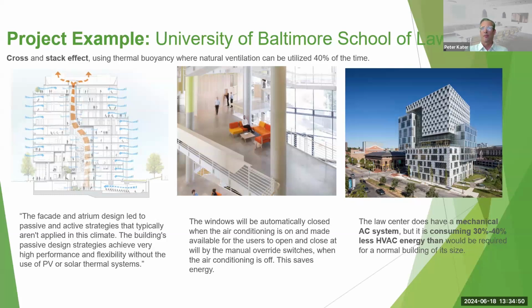Now, in this particular project, they opted not to use PV solar panels on the roof or solar thermal heating systems. Instead, they used a downsized mechanical ventilation system in combination with the intelligently controlled natural ventilation system, and realized a significant capital cost saving because of that smaller HVAC plant that was needed. The law center is consuming something like 30 to 40% less energy in its mechanical ventilation system than if that system was operating alone and had been sized to operate without natural ventilation.